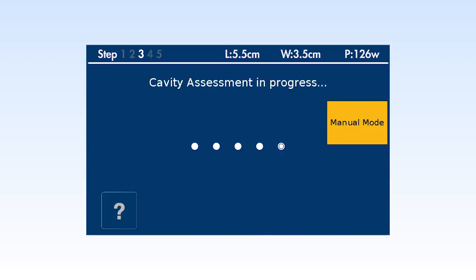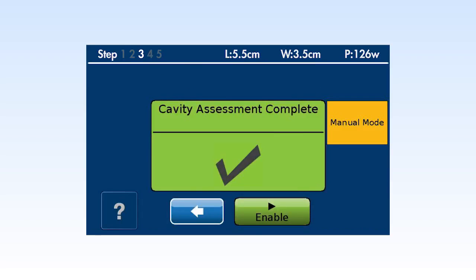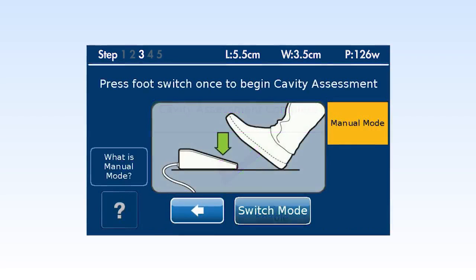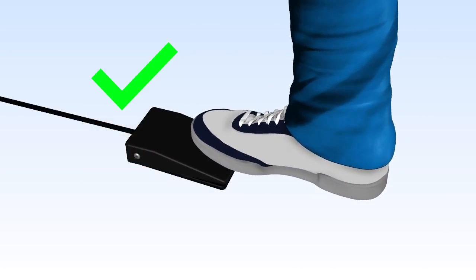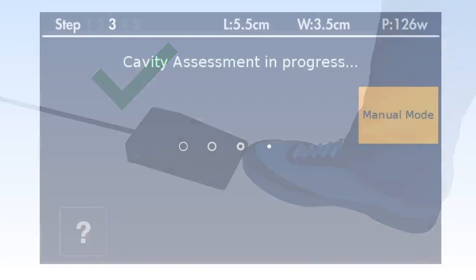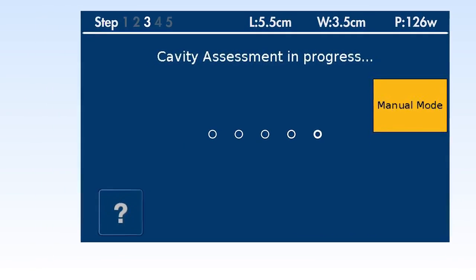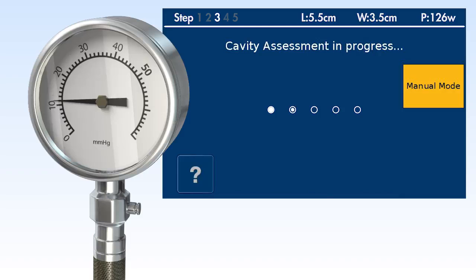In the default manual mode, you will be required to press the Enable button on the controller after the successful completion of the cavity integrity test. Begin the Cavity Integrity Assessment Test, or CIA test, by stepping on the foot pedal once and then releasing the pedal. To pass the Cavity Integrity Assessment Test, the system must be able to hold a pressure of 50 millimeters of mercury for 4 seconds. The test is sensitive enough to detect a perforation as small as an 18-gauge needle.